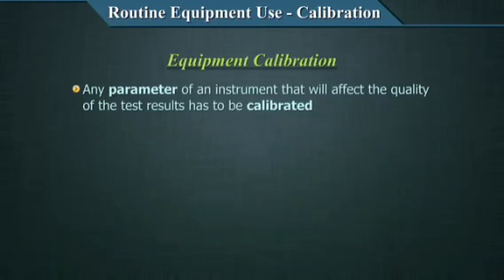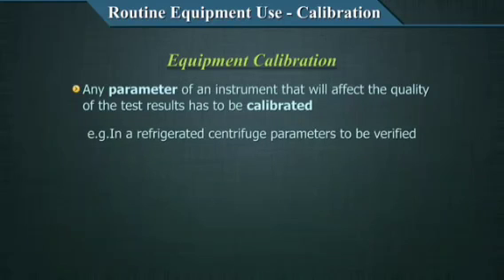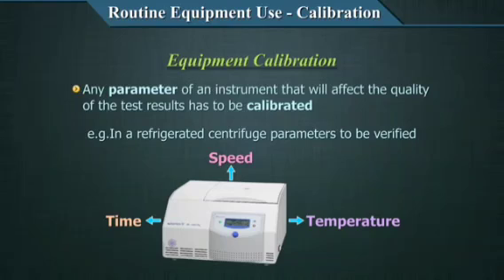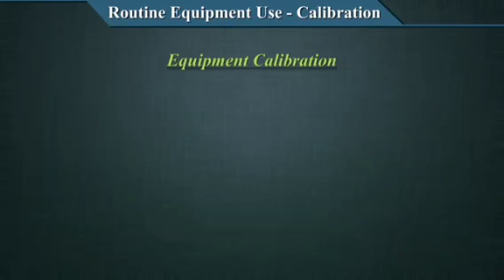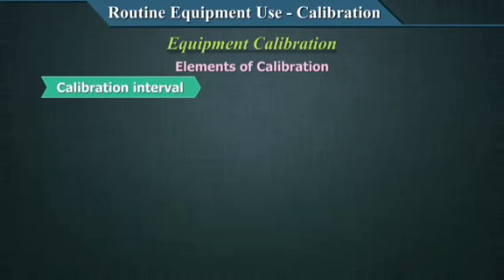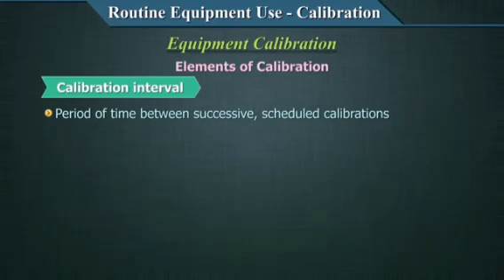Any parameter of an instrument that will affect the quality of the test result has to be calibrated. Example, in the case of a refrigerated centrifuge, the parameters to be verified are speed, time, and temperature. I hope you have understood that concept. Any parameter, any aspect of an instrument which will affect the quality will require periodic verification for accuracy. This process is called calibration. Certain basic elements to be addressed as part of calibration are, first one is the calibration interval. How often do you calibrate? The period of time between successive scheduled calibrations.